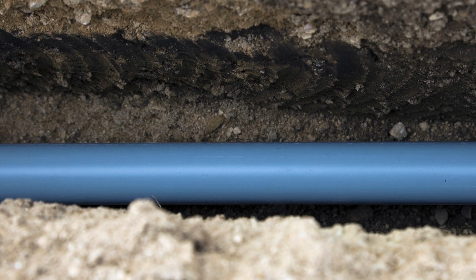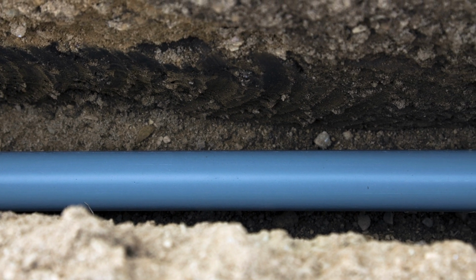If you have exposed direct burial cabling, you're susceptible to digging, people with shovels or a track hoe, whatever equipment, anytime they penetrate the surface of the ground your cable is that much more vulnerable. If you add PVC, you're not only protecting it from digging or cutting with machinery, it also helps with moisture. The direct burial stuff will last longer than just regular riser cable underground, but it does degrade over time too.